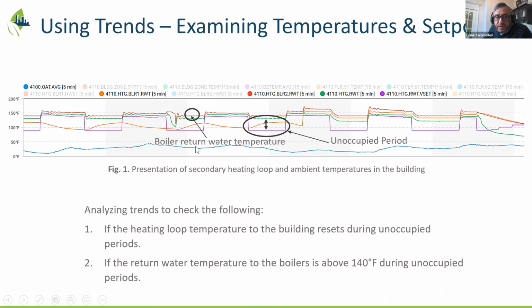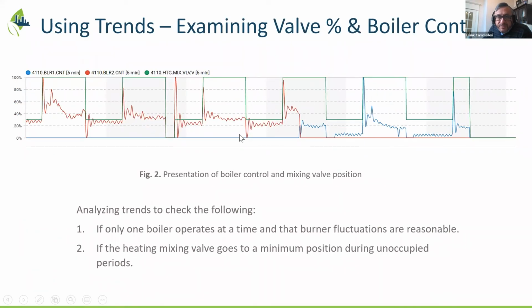The same thing applies on the return water temperature side, item number 2. We have this line, which is the boiler return water temperature to boiler number 2 in this specific facility. You can see here's the 150 degree range, and here is in and around the 140 range. With the CSV files you get from the trends, you can see whether it is actually going below 140. So that's how trends can be useful when it comes to temperatures and set points. Wanted to give you a taste for other types of analysis too. Same building here, but a different part of the sequence that we're testing.